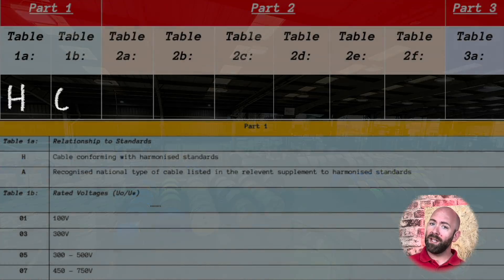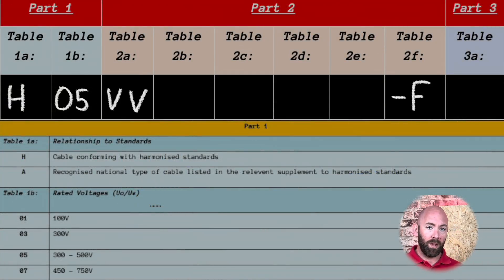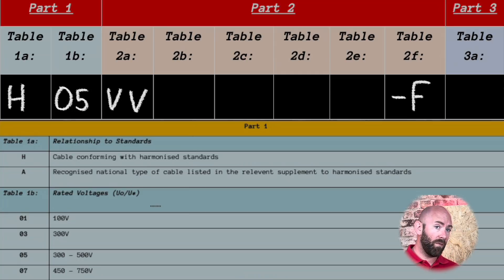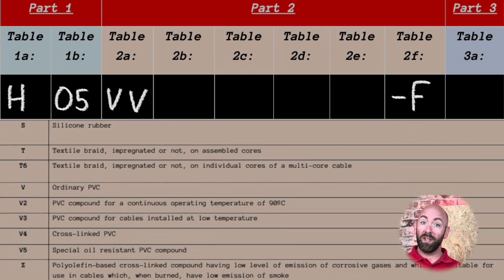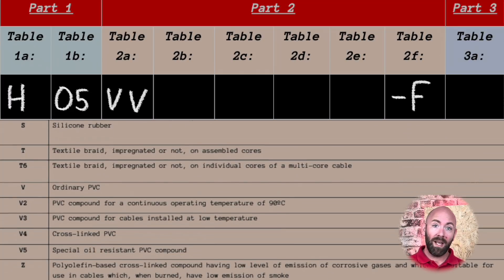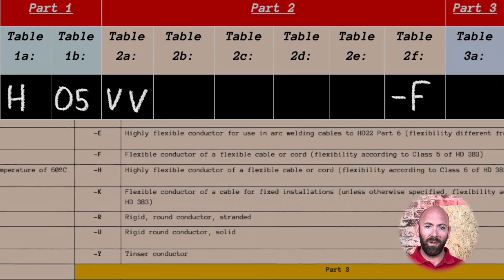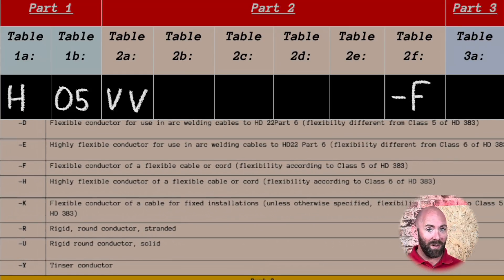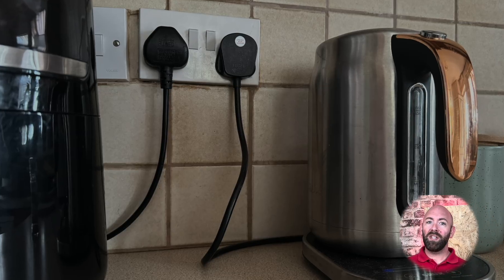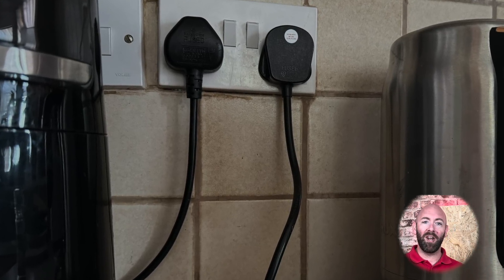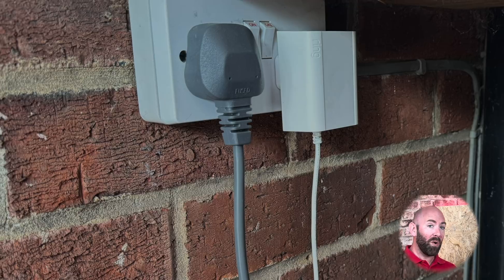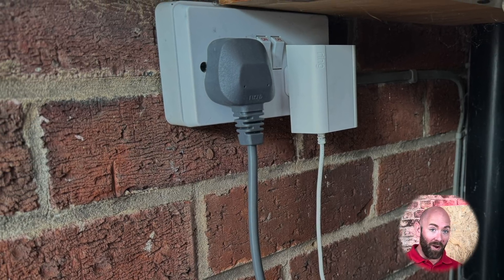No problem. The H tells us it's a harmonized cable. The 05 gives it a voltage of 300 to 500 volts. The V is an ordinary PVC insulation, with the second V being a PVC outer sheath. And finally, the F is a flexible cable. If you're still not sure what this cable is — you will know it, as it's pretty much every appliance standard cable that we have in our home, from the kettle to the washing machine. It's the standard we find on them all.